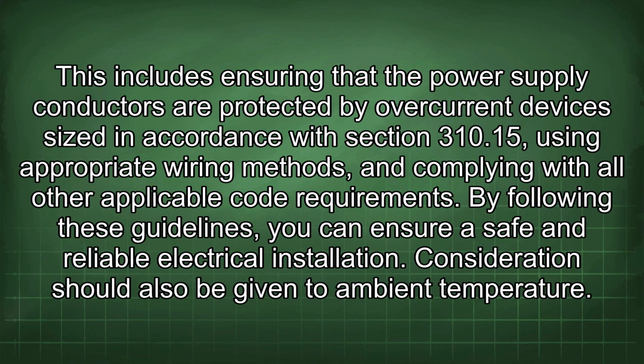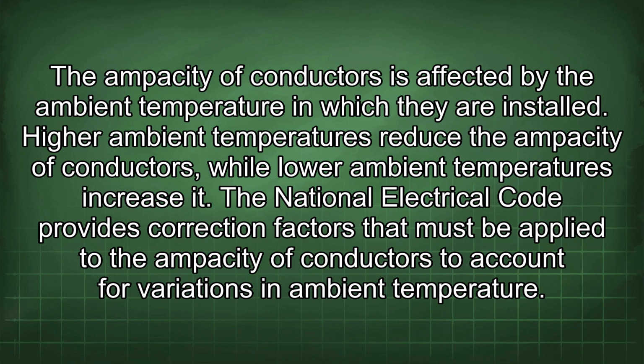This includes ensuring that the power supply conductors are protected by overcurrent devices sized in accordance with Section 310.15, using appropriate wiring methods, and complying with all other applicable code requirements. By following these guidelines, you can ensure a safe and reliable electrical installation. Consideration should also be given to ambient temperature. The ampacity of conductors is affected by the ambient temperature in which they are installed. Higher ambient temperatures reduce the ampacity of conductors, while lower ambient temperatures increase it.